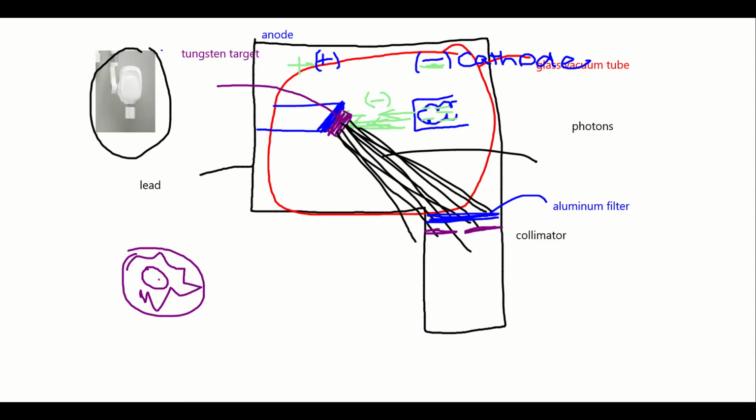So let me type this out. It's made out of lead. So where's the radiation able to come out? The radiation is only then able to come out of the hole right here. And the hole is made the right size for the length of the cone, or the PID, so that when the radiation comes out of that hole, it spreads out, and by the time it hits the end of your PID or your cone, the width right here is 2.75 inches, and that's something that you do need to remember.